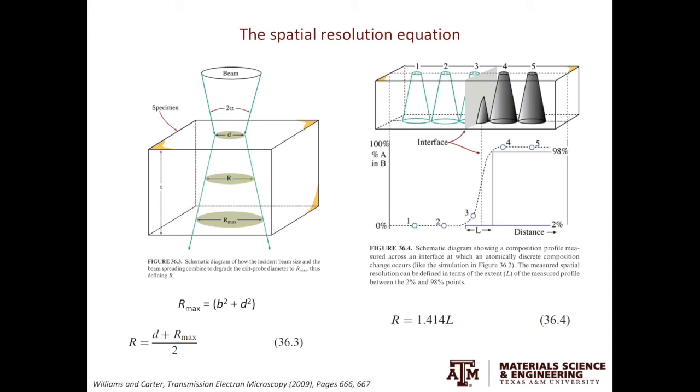In the previous slide, we discussed how we can quantify the beam spreading. But how can we link the beam spreading to the resolution of EDS in TEM? On the left of the slide shows you a pictorial view. As T, the sample thickness increases, the beam spreads more and more, giving you a cone-shaped interaction volume.